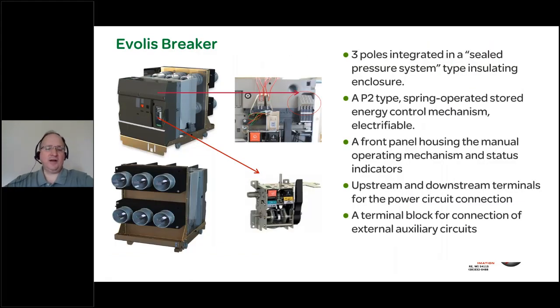It shares its operating mechanism and accessories, like the shunt trip accessory, with the Schneider Electric low voltage Masterpact circuit breaker line. So if you look at the Evolis breaker, it looks like a big brother, or the larger version, of the Schneider Electric Masterpact low voltage circuit breaker. And I could be wrong here, and I'd love to be corrected, but I believe it's the only circuit breaker line currently available that shares a common mechanism as well as accessories between the low voltage version of the breaker and the medium voltage version of the breaker, which is the Evolis vacuum breaker you see here.